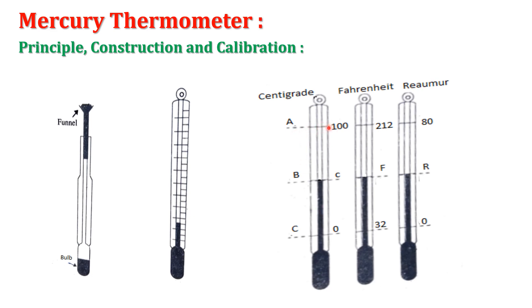For marking the upper fixed point, the thermometer is kept in a special steam chamber called a hypsometer. When water boils in the hypsometer and reaches the temperature of steam at about 100°C, mercury rises slowly and attains a particular level. That level, at about 100°C, is marked as the upper fixed point.